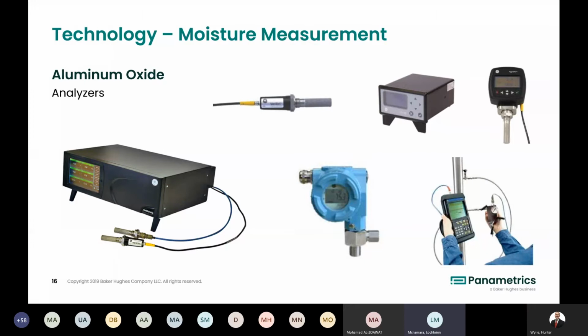And then the last one, the one you see in the middle, is called the MMY30. Again, it's another transmitter. It has the advantage of an inbuilt flow cell, which allows you to connect it directly onto process pipes for applications like instrument air, where the pressure isn't too high, but you can make the measurement at the process pressure. All these sensors we saw on the previous slide use the same fundamental technology on each sensor, and you just have different analyzers that they can be connected to.